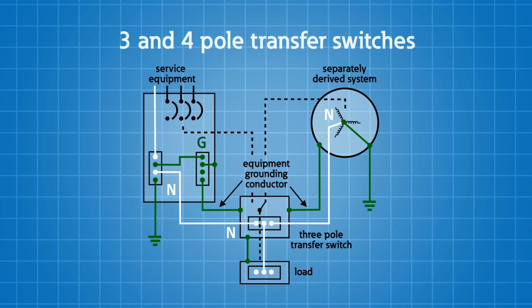The important thing to understand is when you make that connection, you've established a separately derived system. So when I have a neutral conductor bonded and grounded in two separately derived systems, remember I have it grounded and bonded in my service panel, I have it grounded and bonded in my generator, I need to make sure that I only have one place where that occurs, and to get that done, I need to switch the neutral in the transfer switch. So that means I would need to have, say for example, a 4-pole transfer switch. If I do that, I put a 4-pole transfer switch in, I switch the neutral, everything is fine.